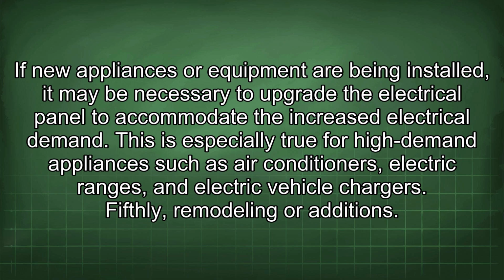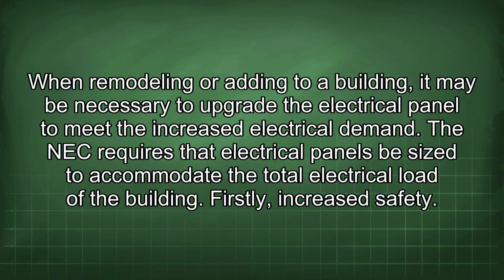Fifthly, remodeling or additions. When remodeling or adding to a building, it may be necessary to upgrade the electrical panel to meet the increased electrical demand. The NEC requires that electrical panels be sized to accommodate the total electrical load of the building.